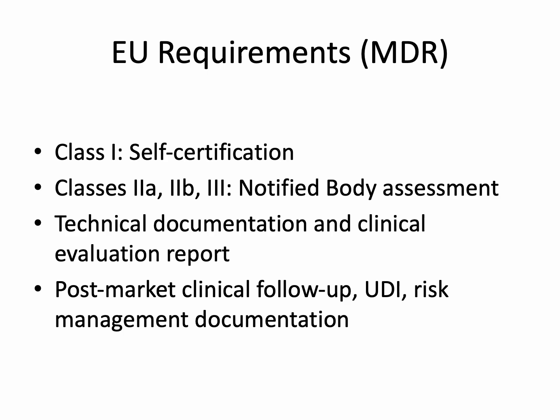The EU MDR classifies devices into classes I, IIA, IIB, and III, with regulatory scrutiny increasing with risk. Class I devices are generally self-certified, while classes IIA, IIB, and III require notified body assessment.